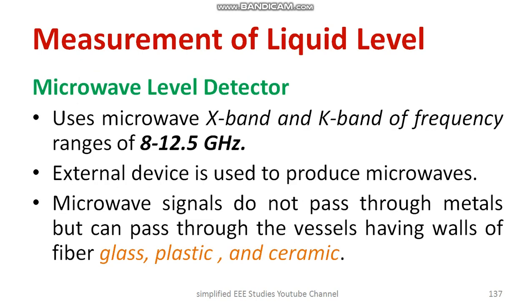Another method is the microwave level detector. Microwave in the X-band and K-band frequency range of 8 to 12.5 GHz is employed. There are different methods to generate microwaves, and an external device is used to produce them. Notably, microwave signals do not pass through metals, but they can pass through vessels made of fiber, glass, plastic, ceramic, etc.